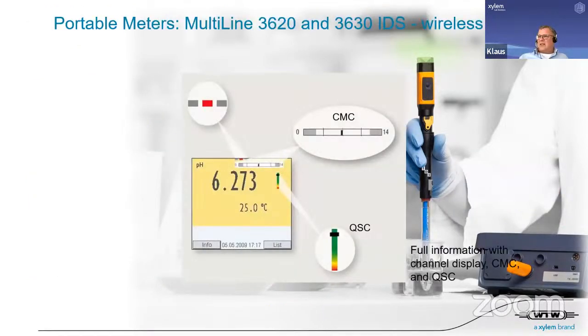Okay, so just a glance at the MultiLine 3620 and 3630. A short look at the display. We have a channel display, that means where my sensors are connected. For instance, this would be the middle connection, with this pH. The color gives me the parameter. That means green is conductivity, yellow is pH, blue is dissolved oxygen, and something called ivory is for the turbidity sensor.